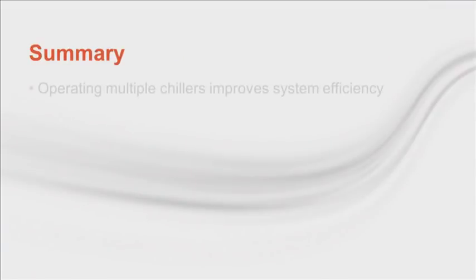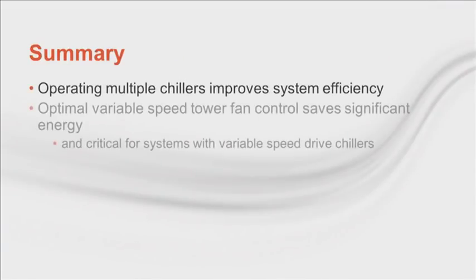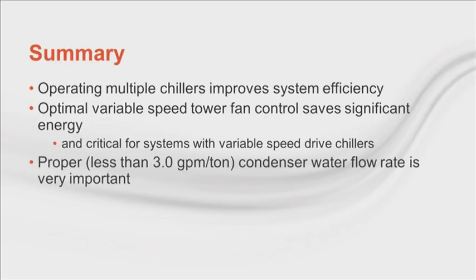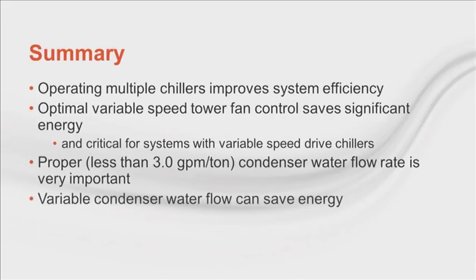Let's summarize all of the conclusions for the condenser side of the system. Multiple chillers improve system efficiency. Optimally controlled variable speed tower fans save a lot of energy, and that control is absolutely critical if variable speed chillers are applied. Proper designed condenser water flow rate is important and allows simpler condenser water control. Variable speed condenser water pump control can save some energy, but primarily on over-designed systems.